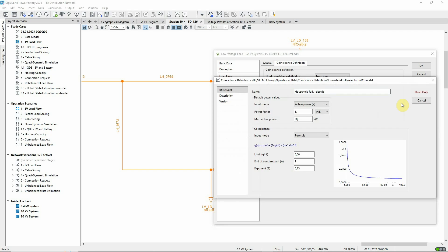The coincidence curve defines what the maximum consumption of a single unit is and how the coincidence decreases over the number of units of the same type. Coincidence curves can be defined using tabular input or a formula. In this case, the formula approach is used.